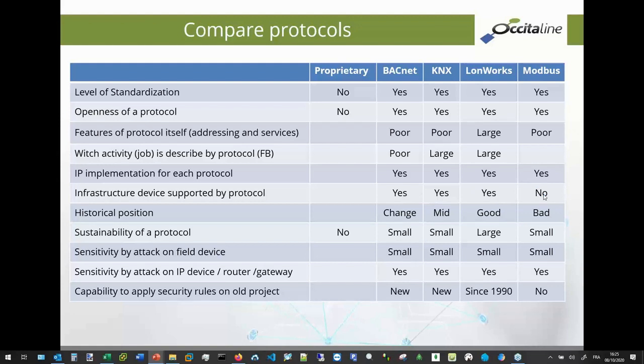IP implementation on the protocol, yes. Modbus, LON, KNX, and BACnet all support IP, but be careful. For example, for KNX, IP devices do not often exist. IP devices exist in BACnet. IP devices exist in LON. IP devices also exist in Modbus.